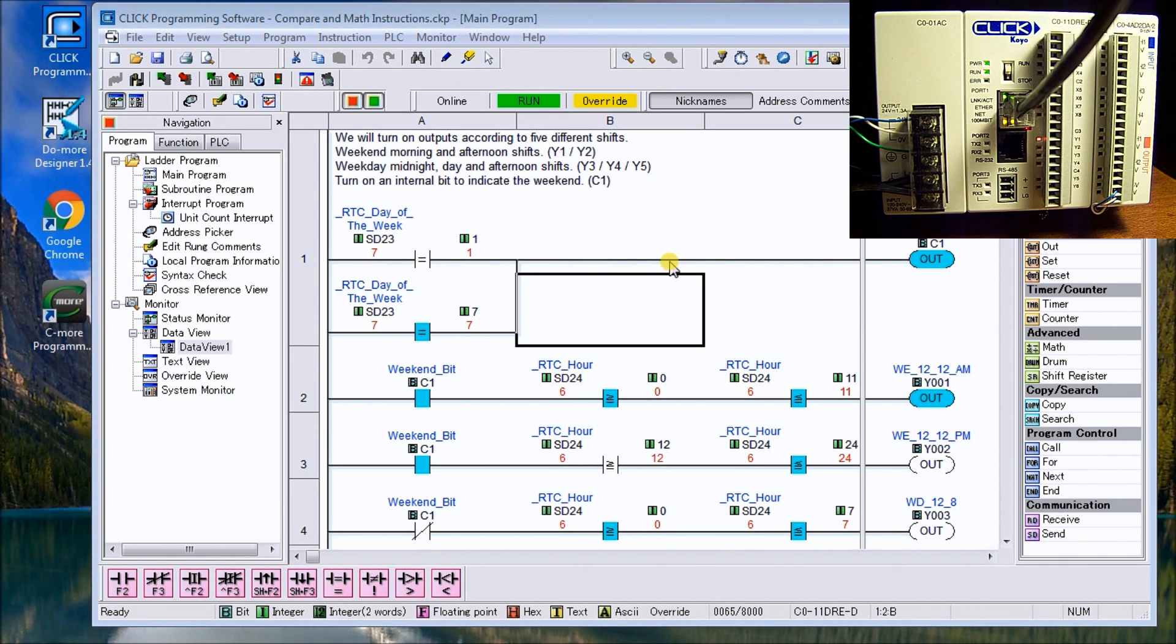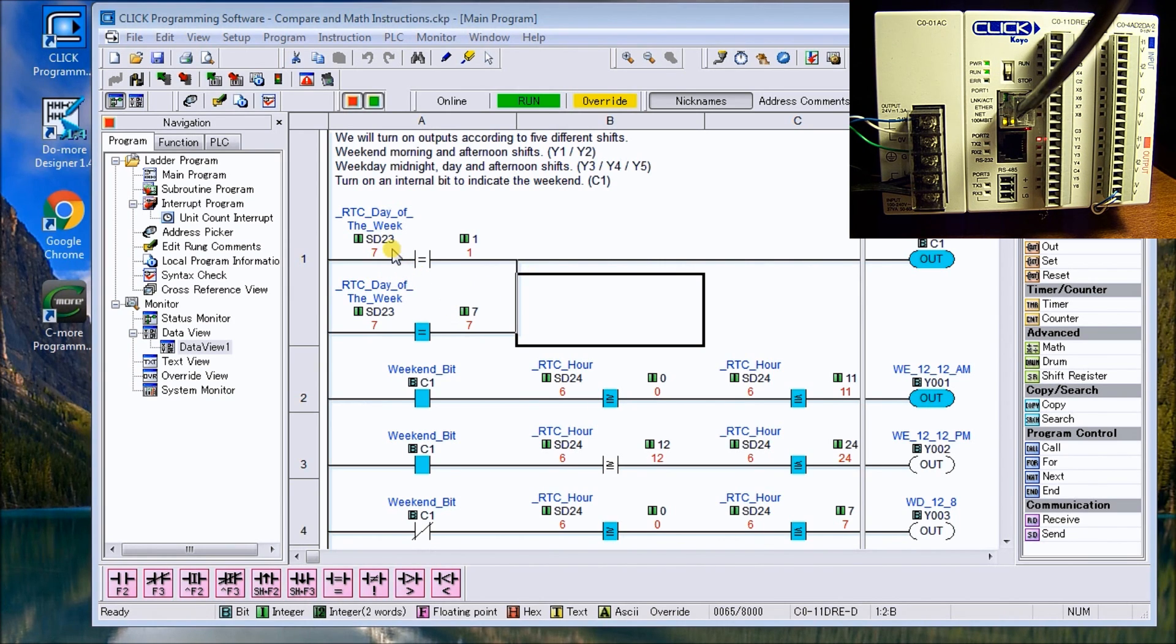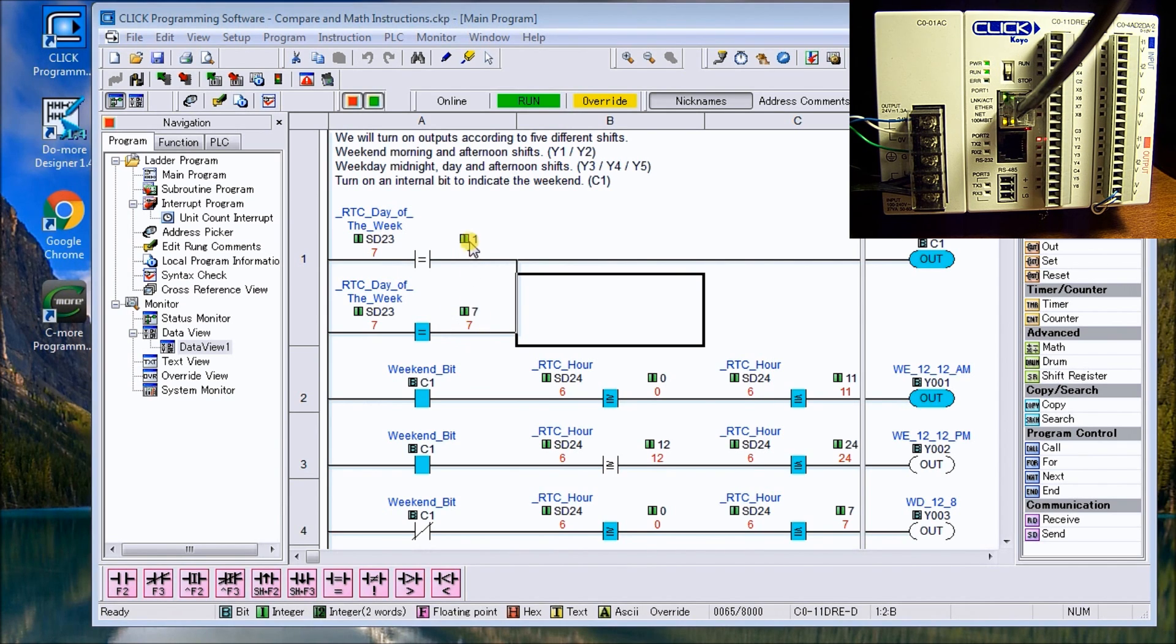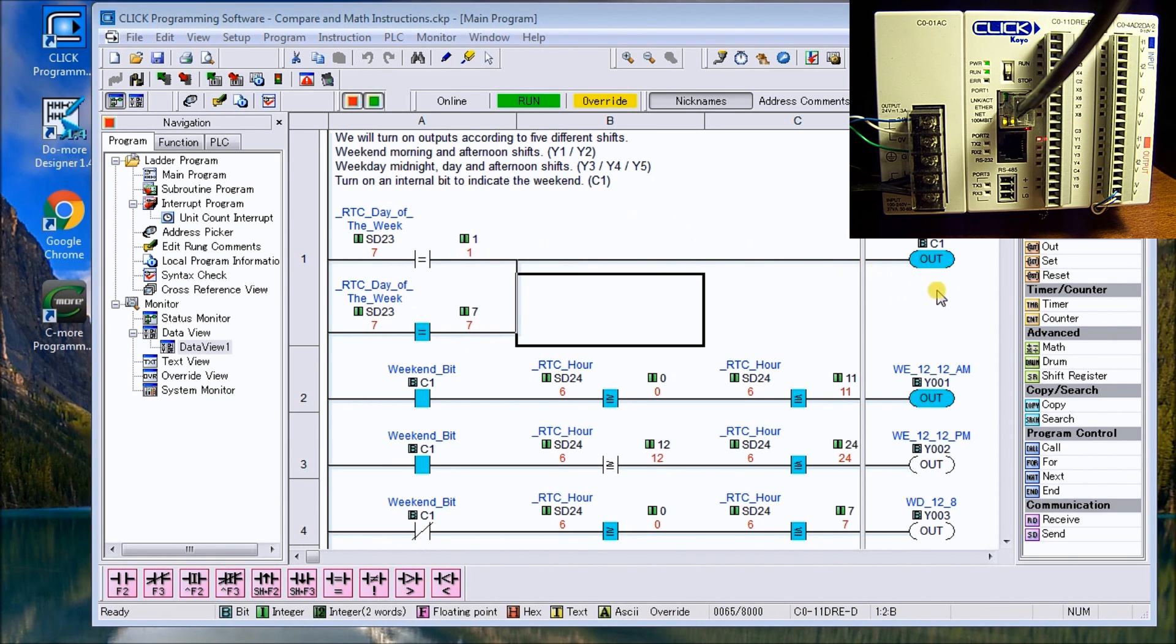And it's going to have the values one to seven indicating the day of the week. And there's our output. So what we do is we first of all determine if it's a weekend bit or not. So in this case here, we compare the SD23, the day of the week to either seven or the value one, seven being the bit for Saturday and one being for Sunday. So as you can see, currently right now it's equal to Saturday and so we have our weekend bit on.